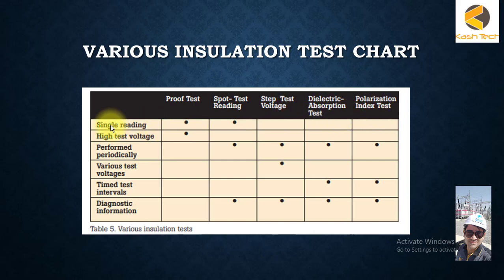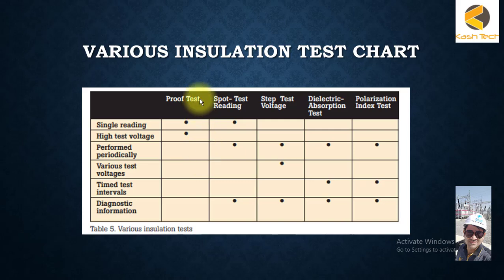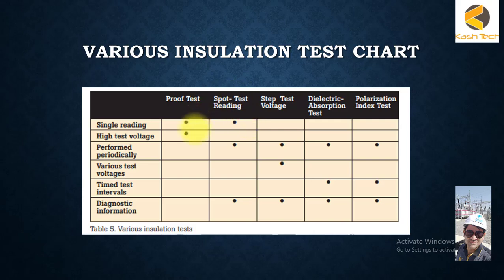The single reading test is done during installation as part of proof testing, and also during maintenance under the name spot test reading. Proof testing is done during installation, while the other four remaining tests are done during maintenance. Single reading is always part of proof testing and is also performed as a maintenance spot test.